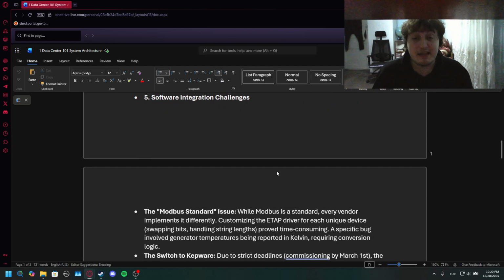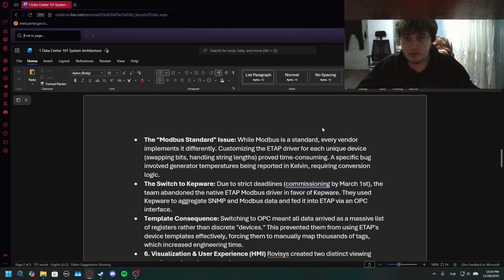Software integration challenges: as the video was saying, while Modbus is a standard, every vendor implements it differently, requiring customizing the ETAP driver for each unique device, swapping bits, handling string lengths - all time consuming. A specific bug involved generator temperatures being reported in Kelvin, requiring conversion logic.